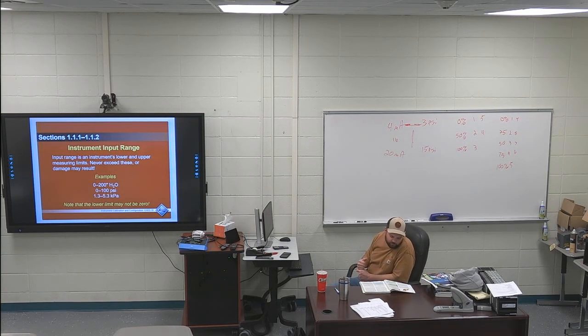Calibration concepts 113, second paragraph is highlighted. An instrument's range consists of its lower and upper input or output limits. For example, if an instrument can measure a process value between 60 inches of water and 400 inches of water, its range is 60 to 400 inches of water. Similarly, if an instrument can output a pressure between 3 and 15 psi, its range is 3 to 15 psi. Fascinating stuff, right?